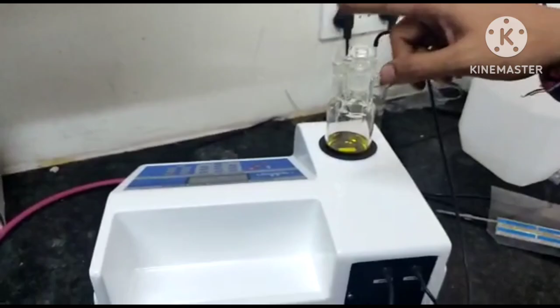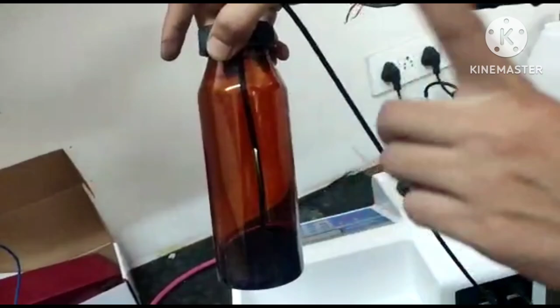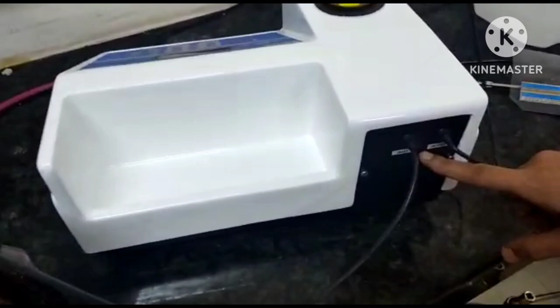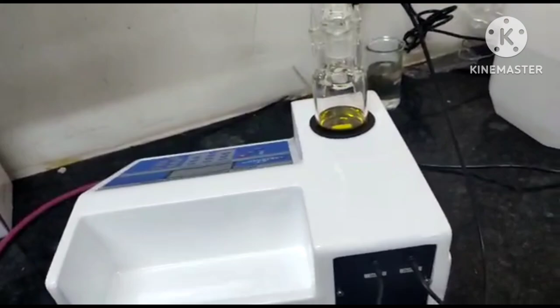If the solution is not dropping from this to this one, then first we need to check whether the pipe is connected with the internal pipe or not. See, one pipe is going inside. If there is no pipe connected, then you must connect a pipe from the cap to the bottom of the bottle, inside the bottle, and with the same connector connect it to the input line. If all connections are done and the solution is still not coming in the titration vessel, it is not dropping, then you have to open it from here.